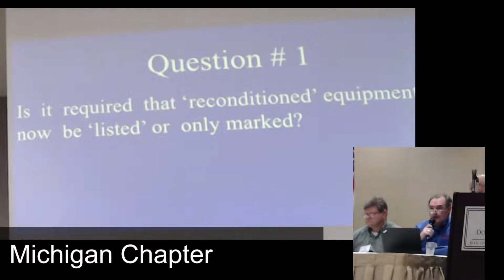So in the 2017 code, they did not require you to remove that label, the original listing mark, in the 2020 code too. So the only way to verify a piece of equipment has been listed as reconditioned is if the UL listing or certification mark identifies it as listed, rebuilt, reconditioned, remanufactured.